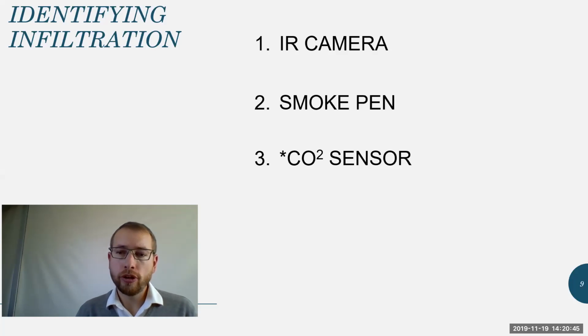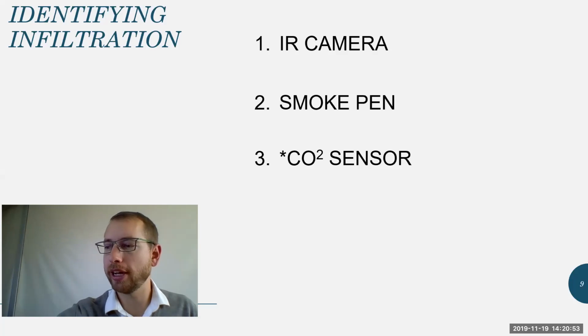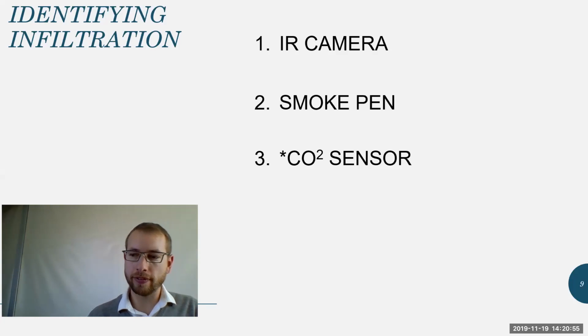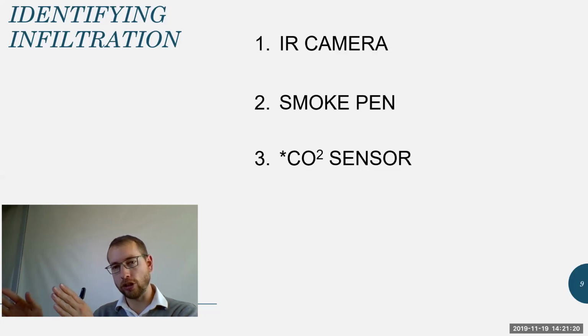If you are worried about setting off smoke alarms, I've never had one go off when I've used one of these because it's from a special material. But even if so, you can use a little bit of baby powder. And I like to do that around windows as well as elevator shafts and just shake a little bit out. It's not as easy to see as the smoke pen, which really does have a high buoyancy and it floats through the air very nicely. The baby powder does really fall a lot, but you can still see it start to drift towards certain areas.